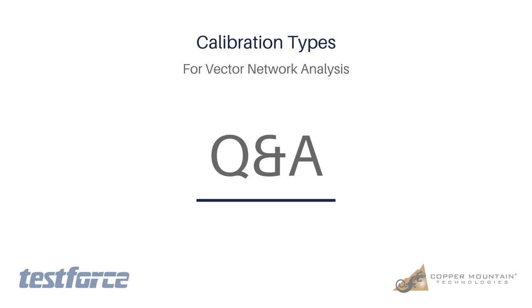I have seen companies that want to test their DUTs very, very fast. They'll set up the segments, and in some cases they might only have 2 points in a segment. And I've seen where the depth that they're testing has things going on in between those 2 points, and they might be passing or failing a component and not really know what's happening. So you have to have the right number of points, and then every point is calibrated in every segment. And each segment can have a different resolution bandwidth. And so there's a lot of interesting things you can do with segments.